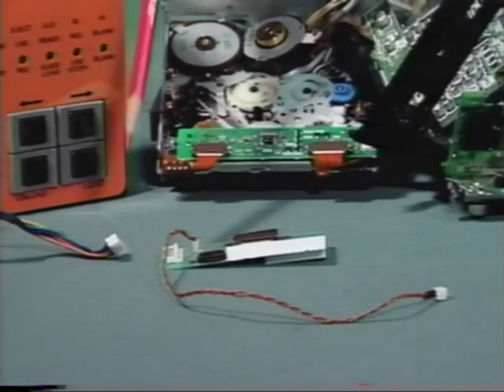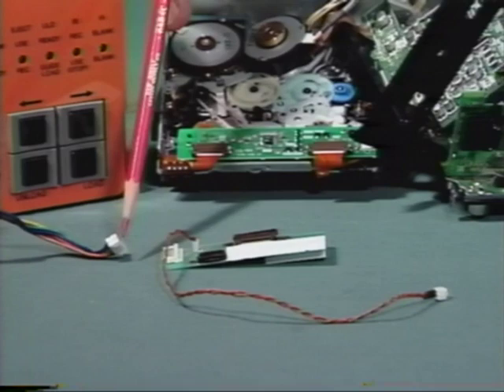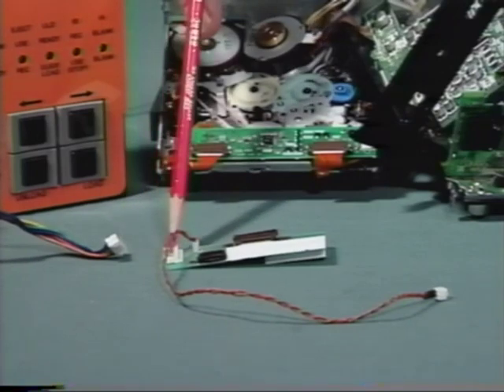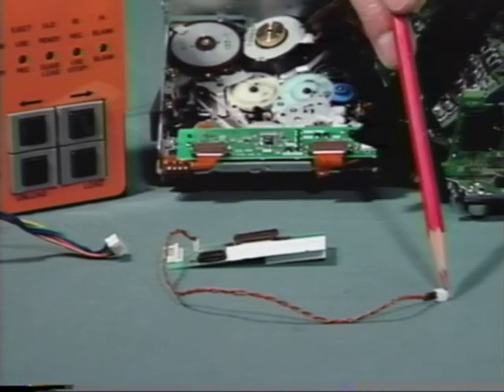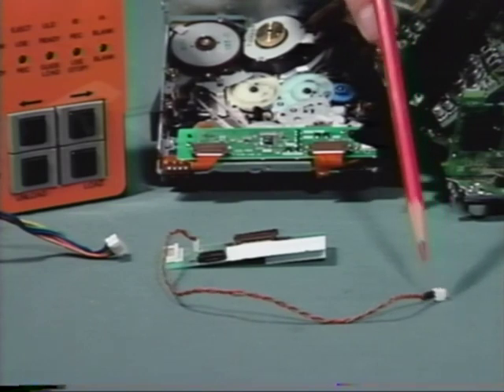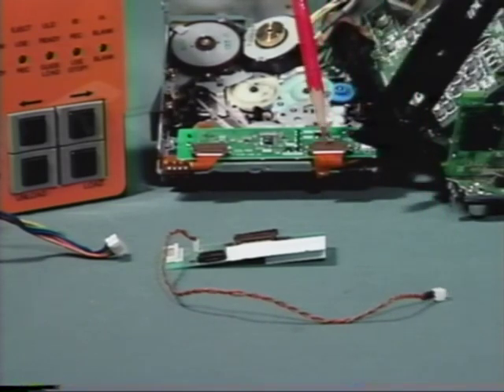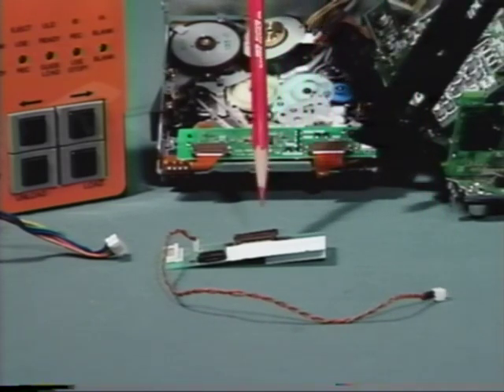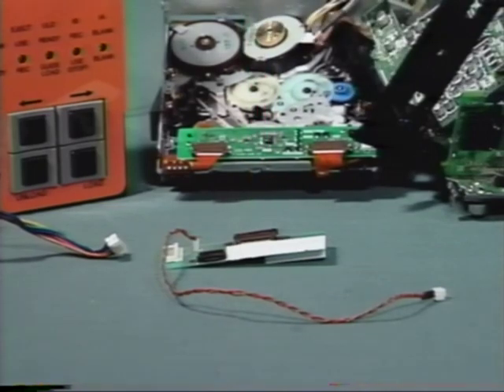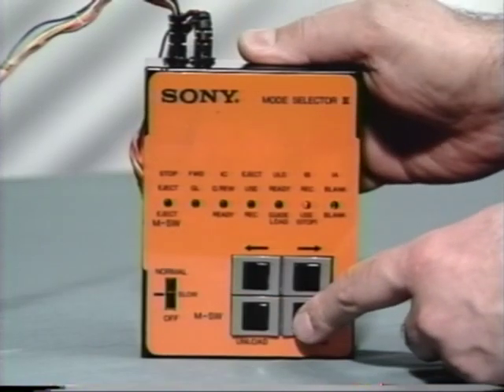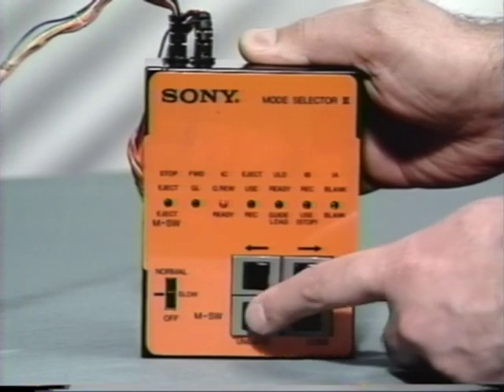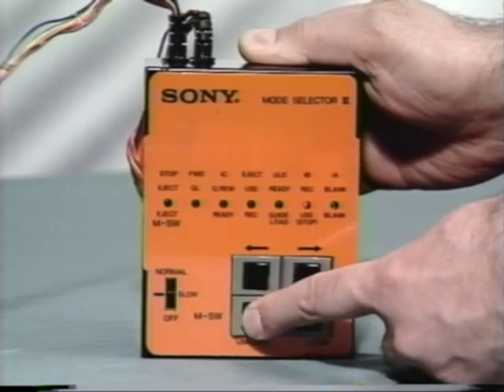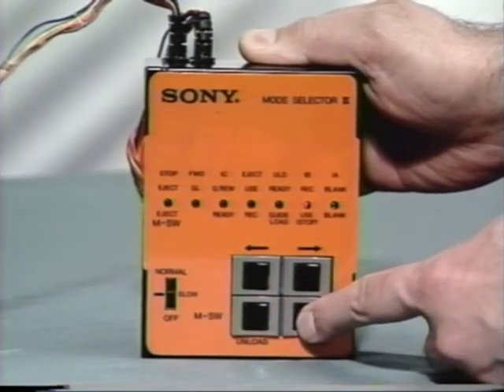With the unit separated, connect the mode box to the adapter board. This time, the 2-pin connector will be used to power the loading motor. Disconnect the mode switch and connect it to the board as well. With the mode box connected, you can check mechanical switch operation by pressing the lower direction buttons.